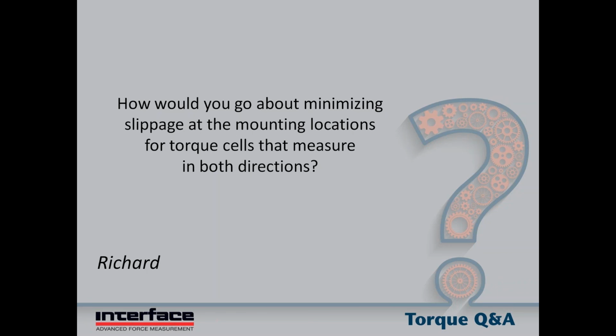If it's a flange type sensor, basically it's the friction between the mating flanges that prevents slippage. So it's not the bolts themselves, it's the bolt tension that creates the friction between the two mating surfaces. And so the friction surfaces have to be clean and dry, for example, and then the torque on the bolts has to be proper, and typically it's using grade 8 hardware and bolts torqued to spec. A lot of cases the mating friction really is maybe less than ideal, and so you have to maximize it by applying as much torque to the mounting hardware as possible. And so you definitely don't want to go on the low side of the torque spec. You'd want to go on the high side.